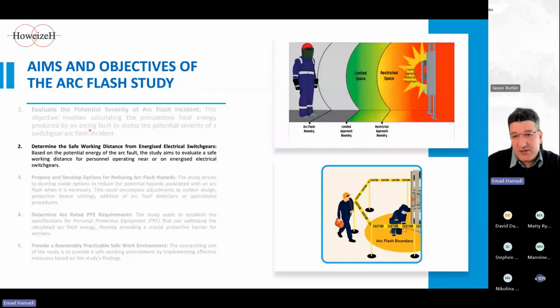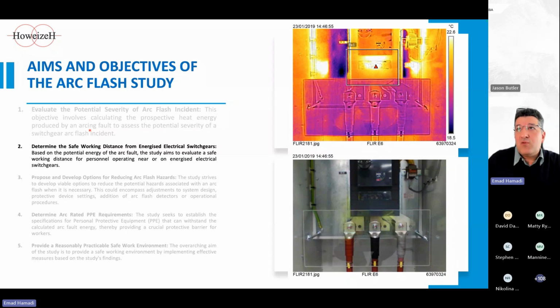The other one, which is one of the critical objectives of the arc flash study, is to determine the safe working distance from the energized electrical switchgear or equipment in general, which is crucial for ensuring the safety of the personnel who operate near or on the energized components. As you know, it's very typical for the operation or maintenance team to undertake routine daily checks near the equipment. Or in many sites, I've seen personnel override the panel lock to open the compartment when it's live for various reasons, such as testing or fault finding, or, as Jason mentioned, in low voltage it's very typical to do thermography. Thermography needs to be done under live conditions, so it's inevitable to open the compartment and get access to it.